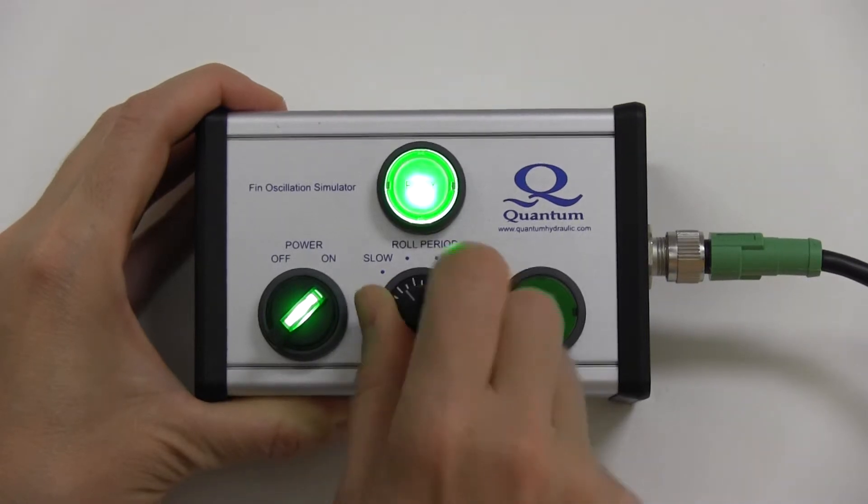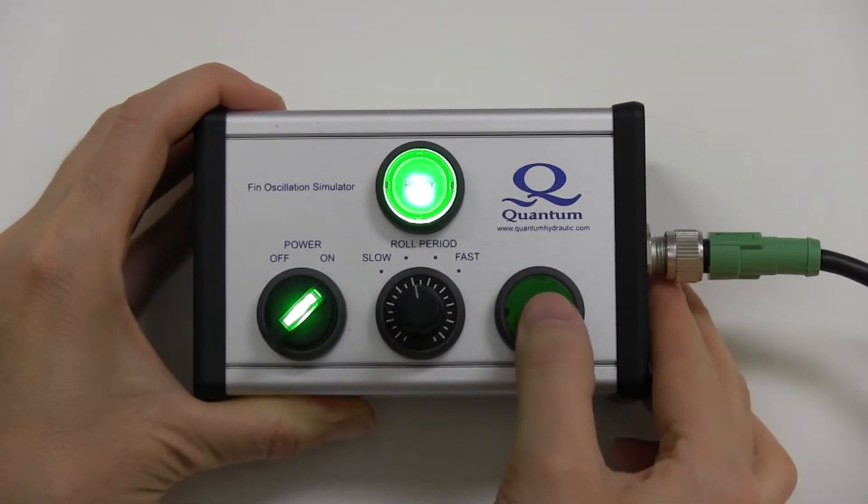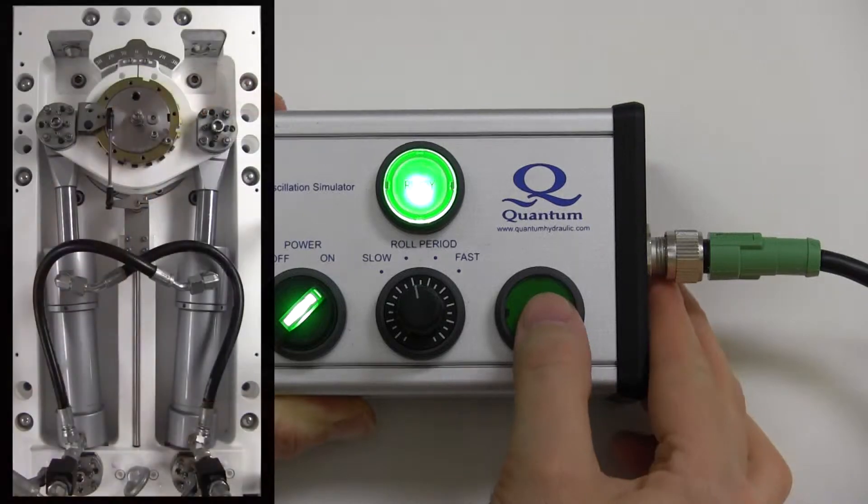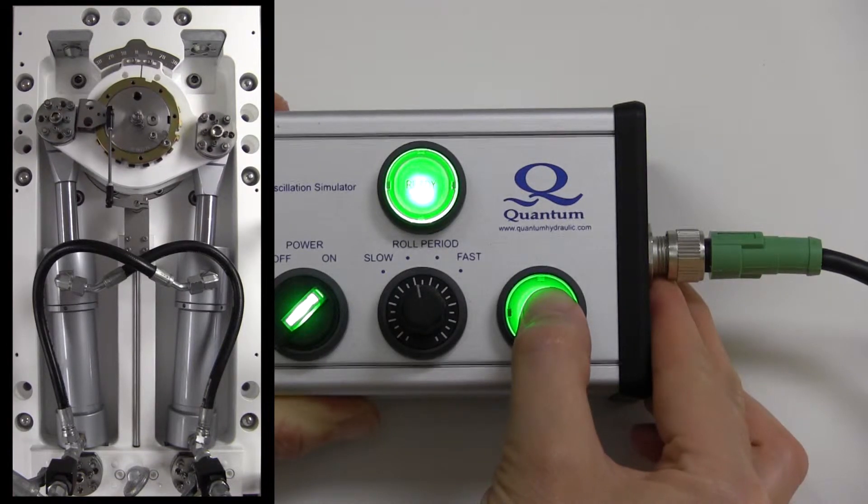To move the stabilizer, set the roll period adjustment on the FIN Oscillation Simulator to the desired oscillation speed. Then press and hold the Move button to cause the stabilizer to oscillate. There are four speeds available.